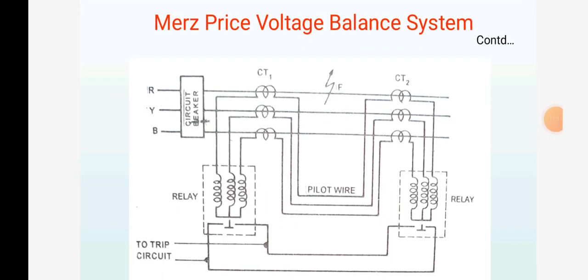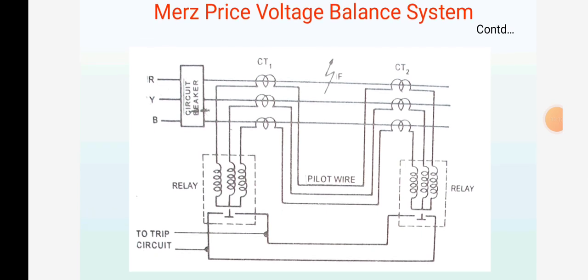This is the diagram for the Merz-Price voltage balance system. It has one circuit breaker, three-phase RYB, three CT1 current transformers and three CT2 current transformers. They are connected with pilot wire, and it has two relays. The relays are connected to the trip circuit.